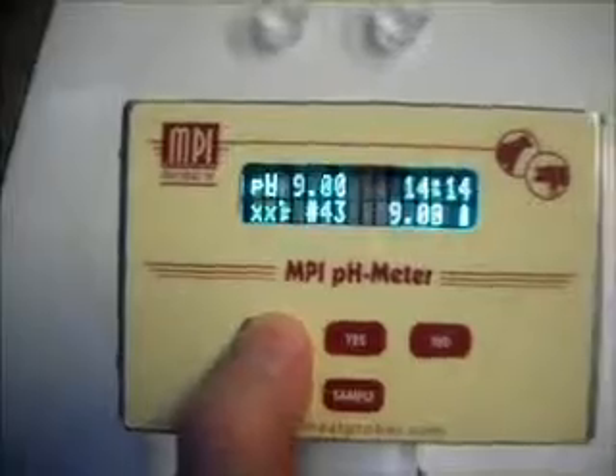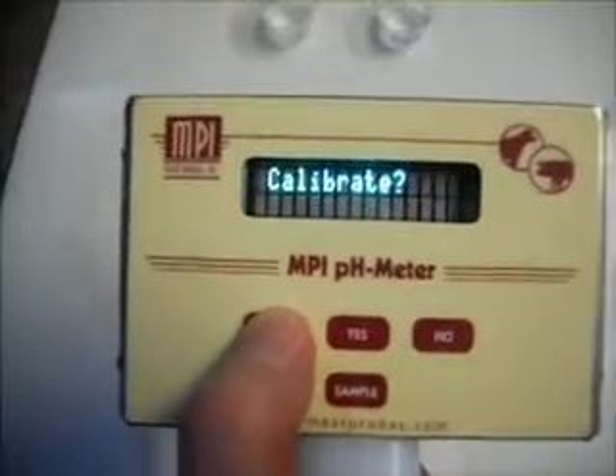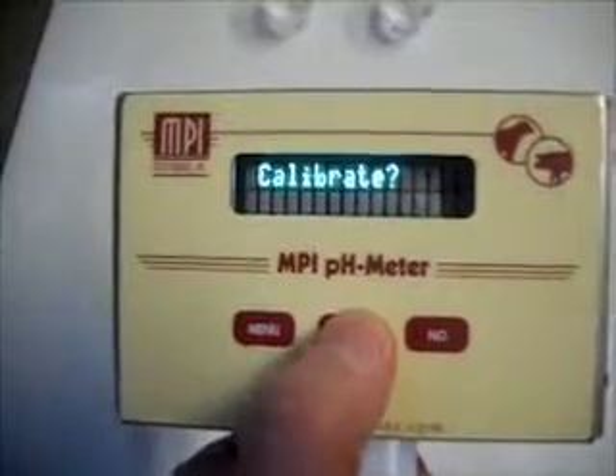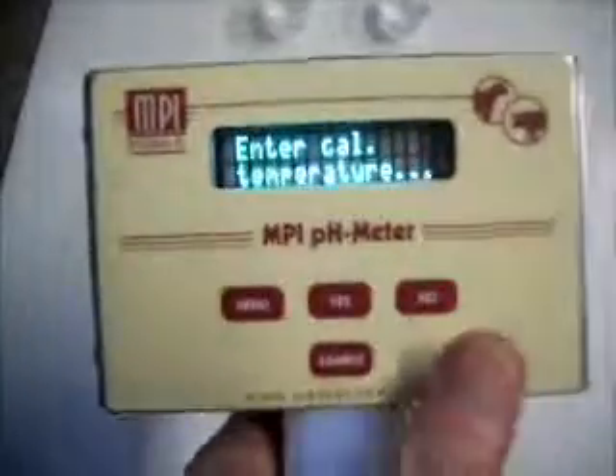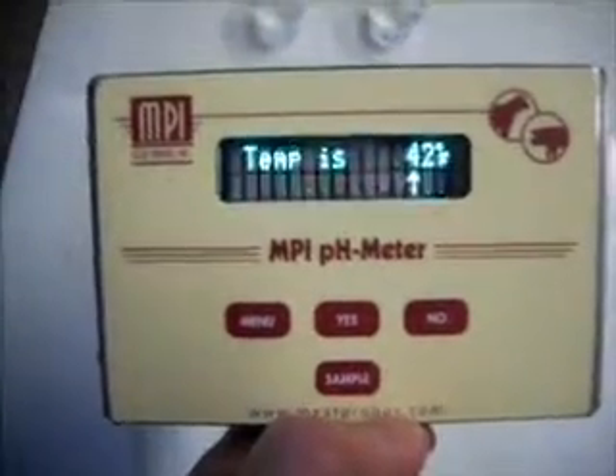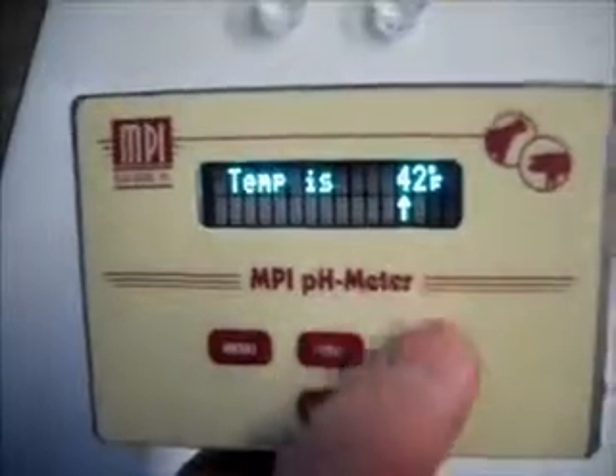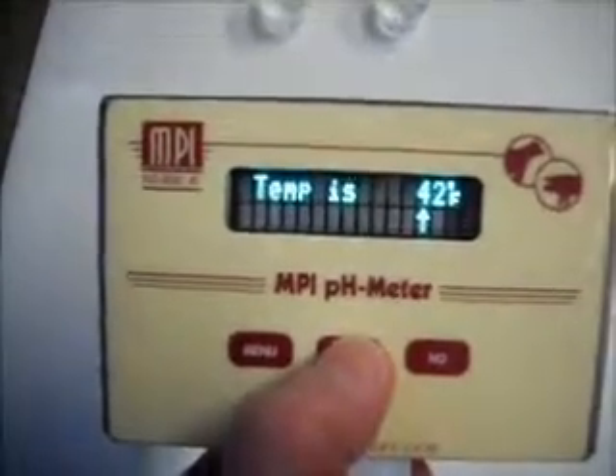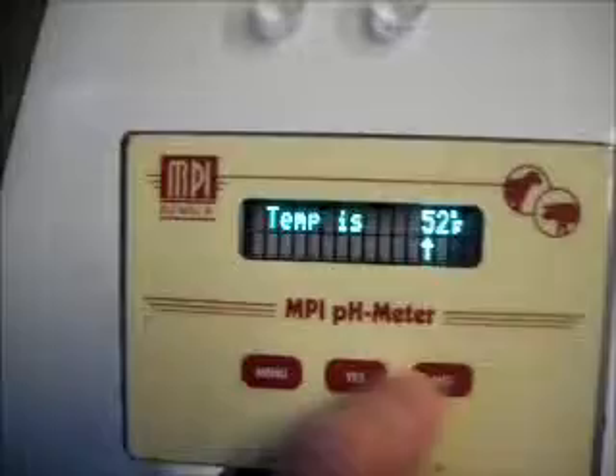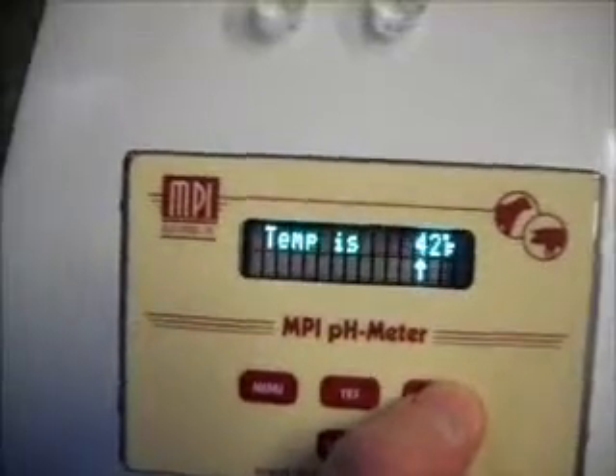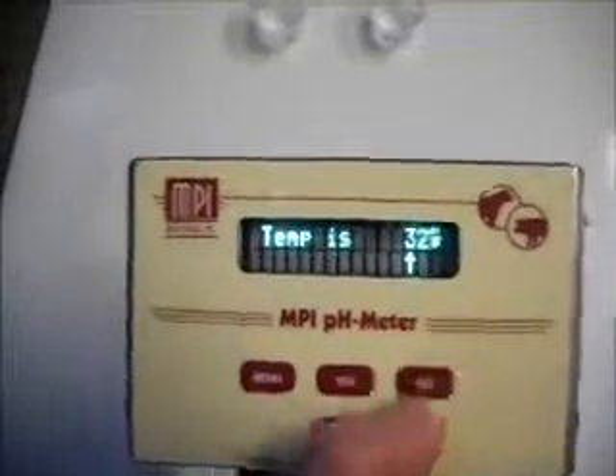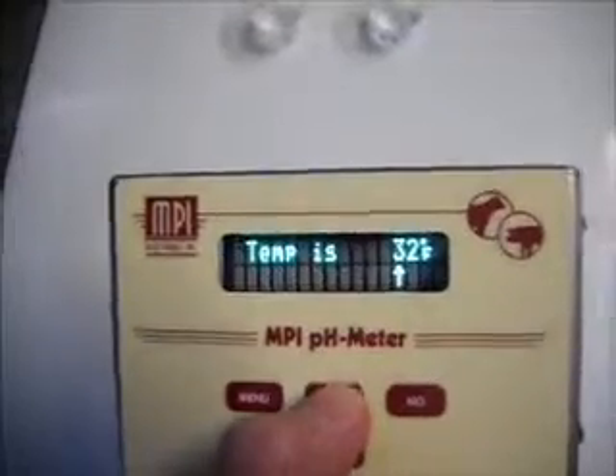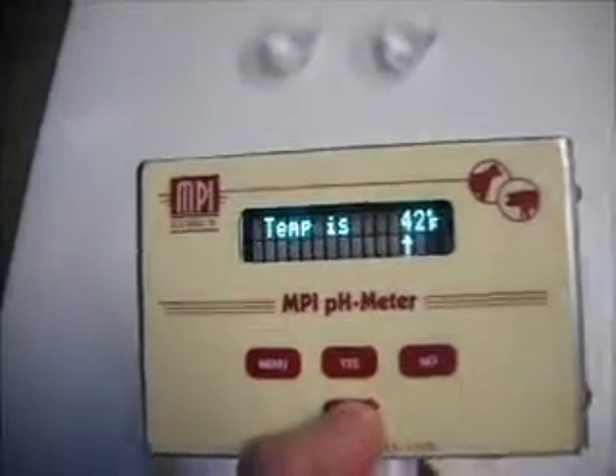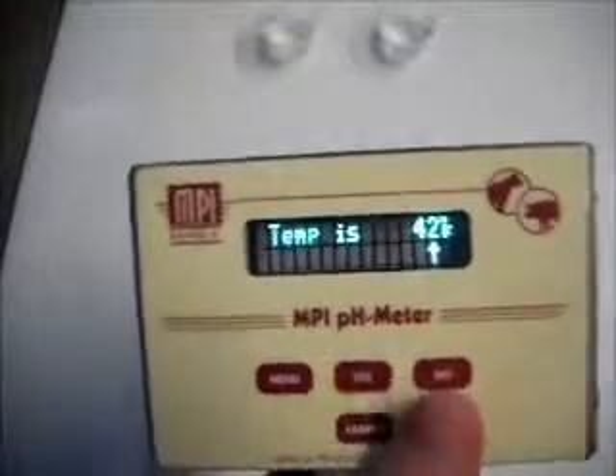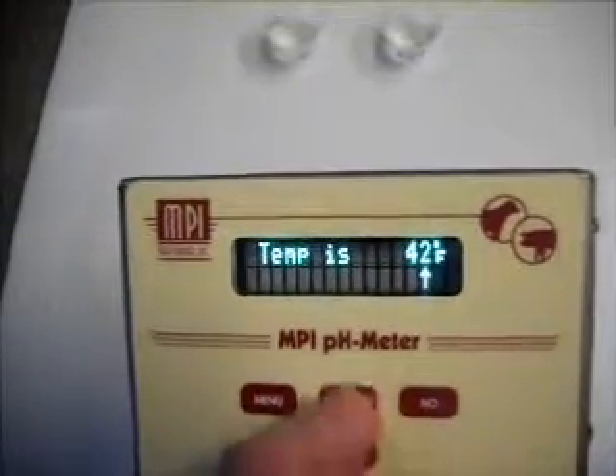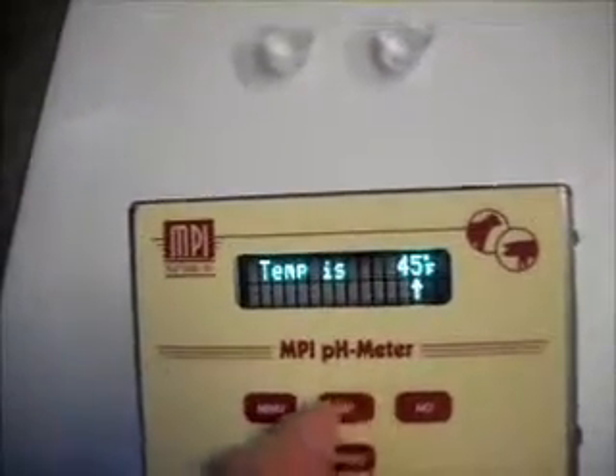So if we press on the menu and tell it we want to calibrate, we get to calibrate. We tell it yes, we want to calibrate. And then it will ask us to enter the calibration temperature. In this case, it's set for 42. We can increment that. We can go to 52, or using the no button, go down to 42, 32, and so on. So let's go with the 42 for now, and then we can go to the next digit and increase or decrease the digit there. We can go to 45, let's say.